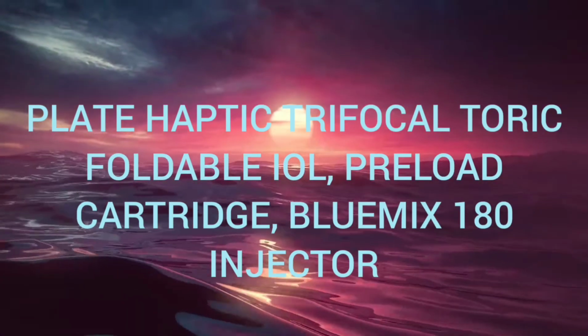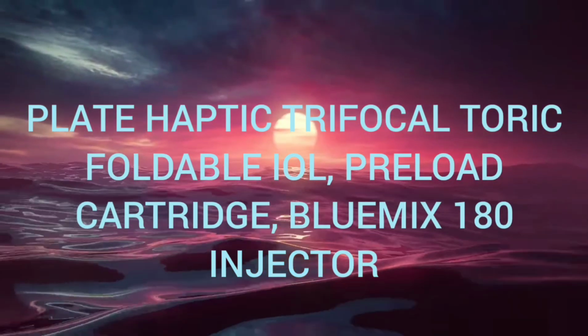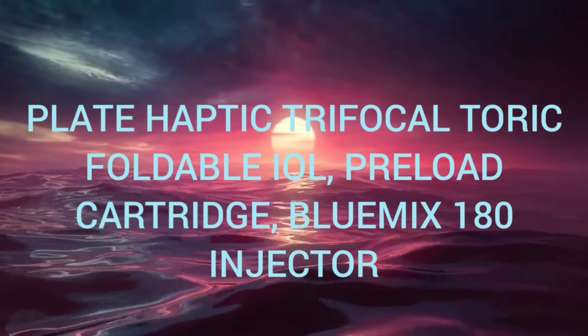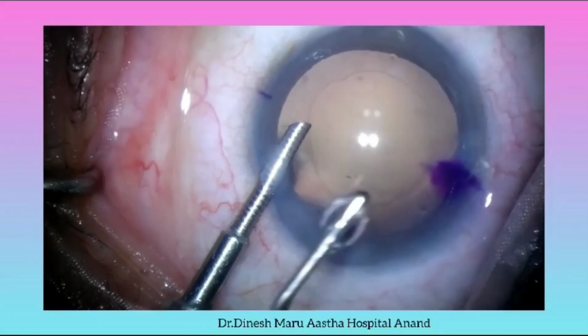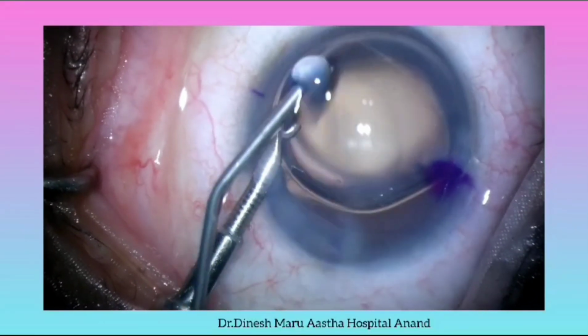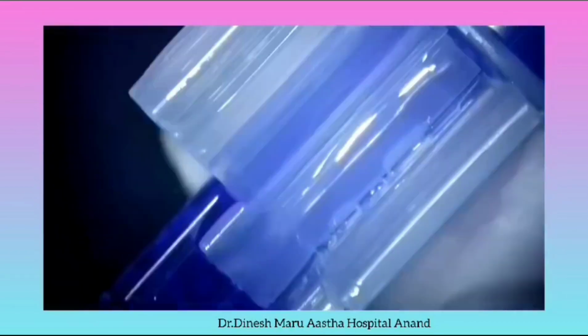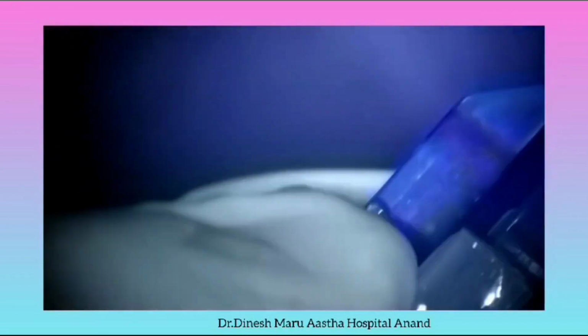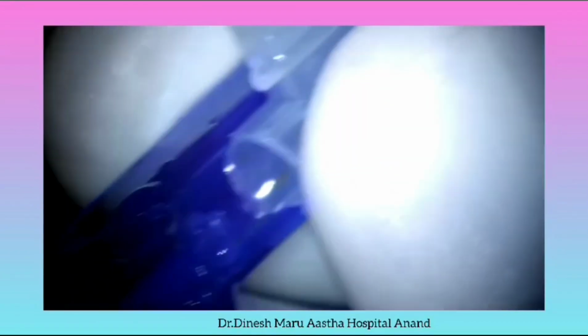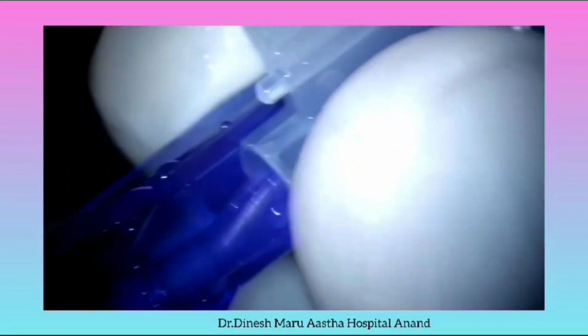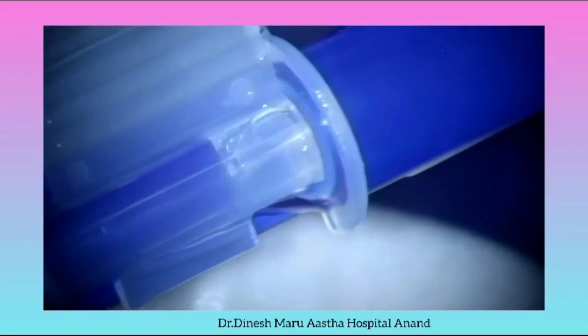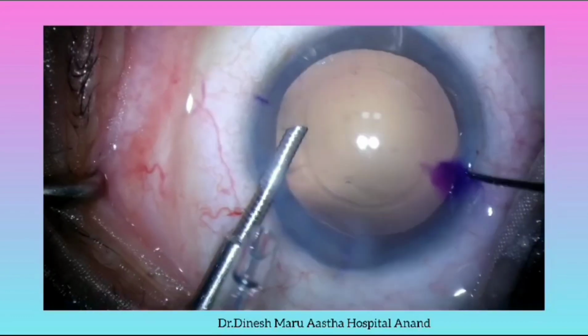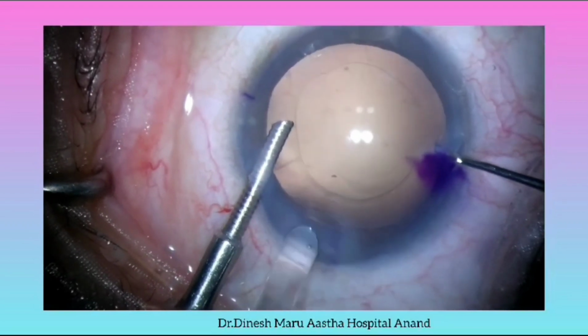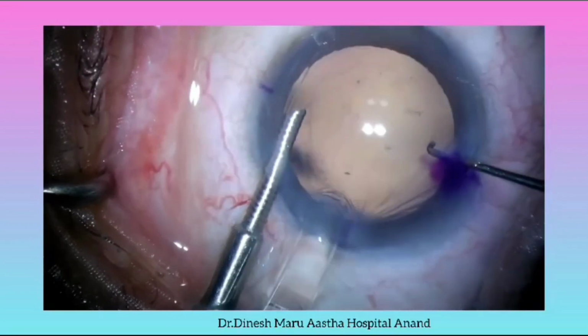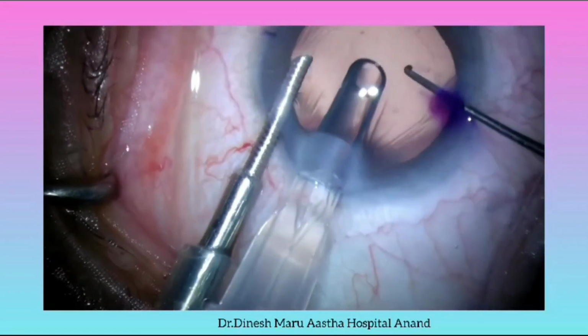Plate haptic trifocal toric IOL preloaded cartridge Blue Mix 180 injector. Ensure the corneal wound matches the 1.8 mm size of the cartridge for seamless insertion. Load the cartridge into the Blue Mix 180 injector for demonstration of smooth delivery as shown in the video. Push the lens using the plunger till you hear a confirming click sound indicating proper locking.